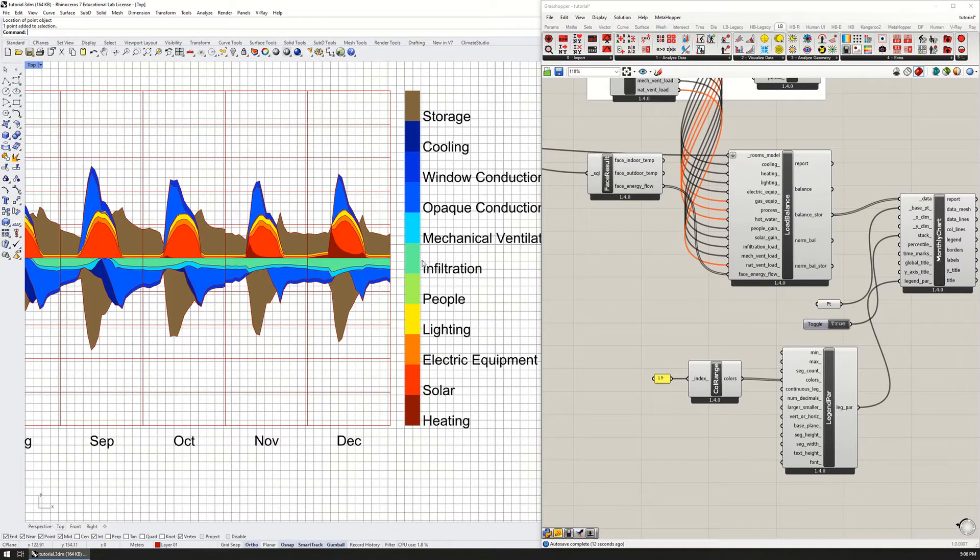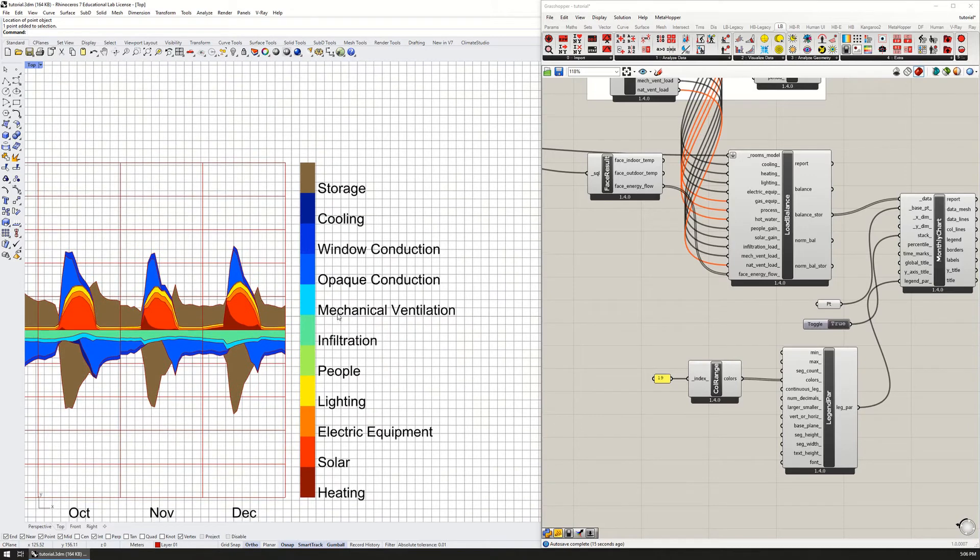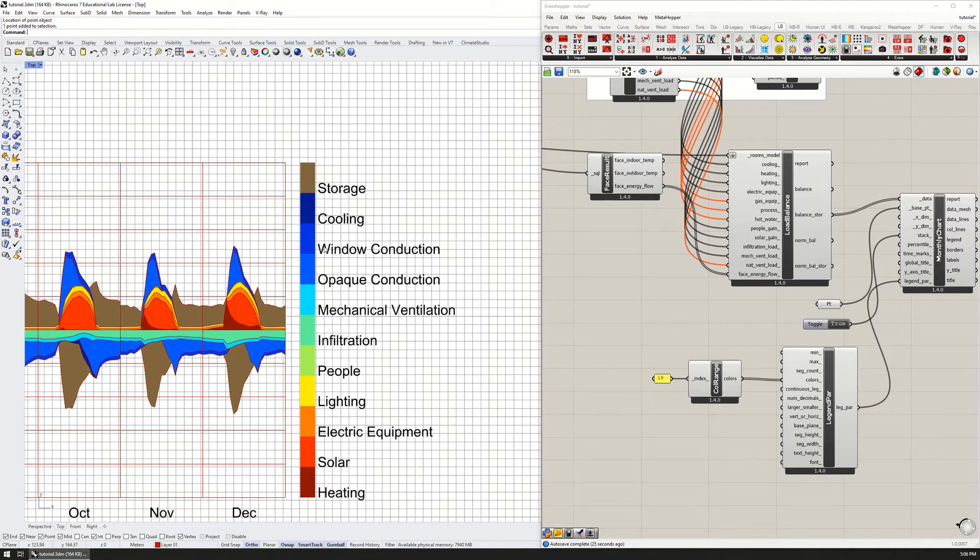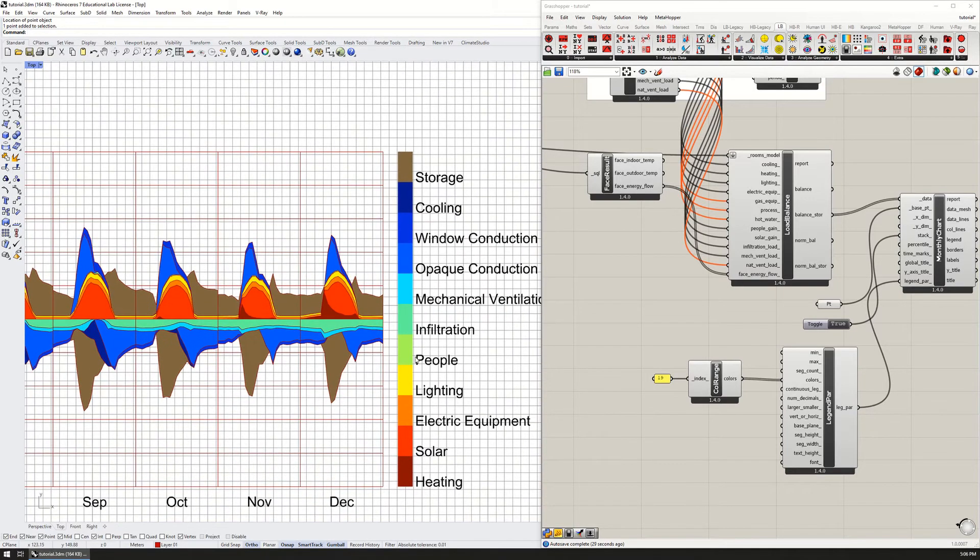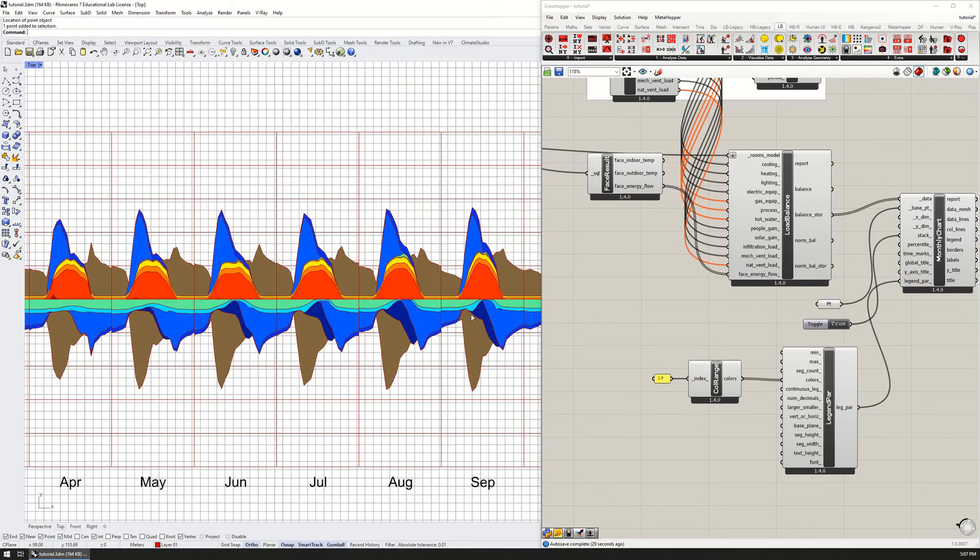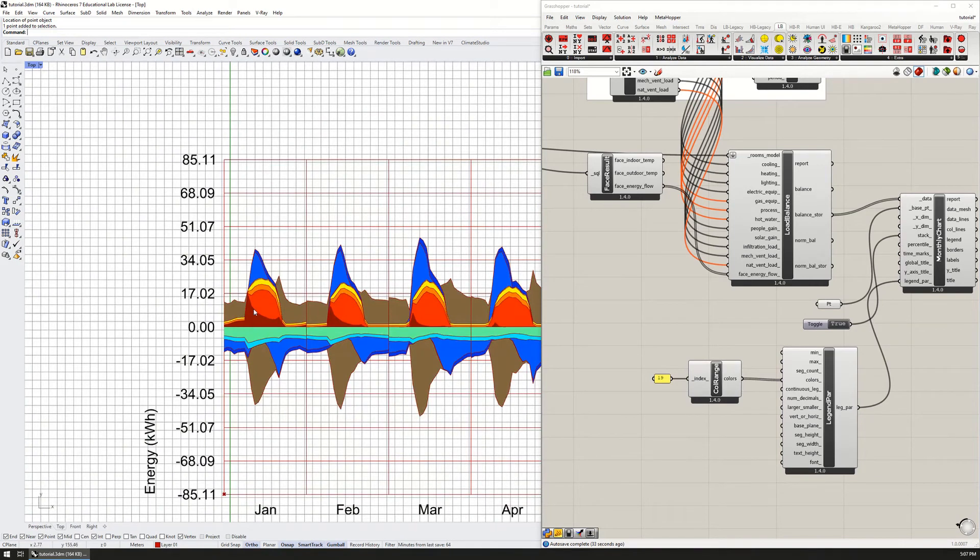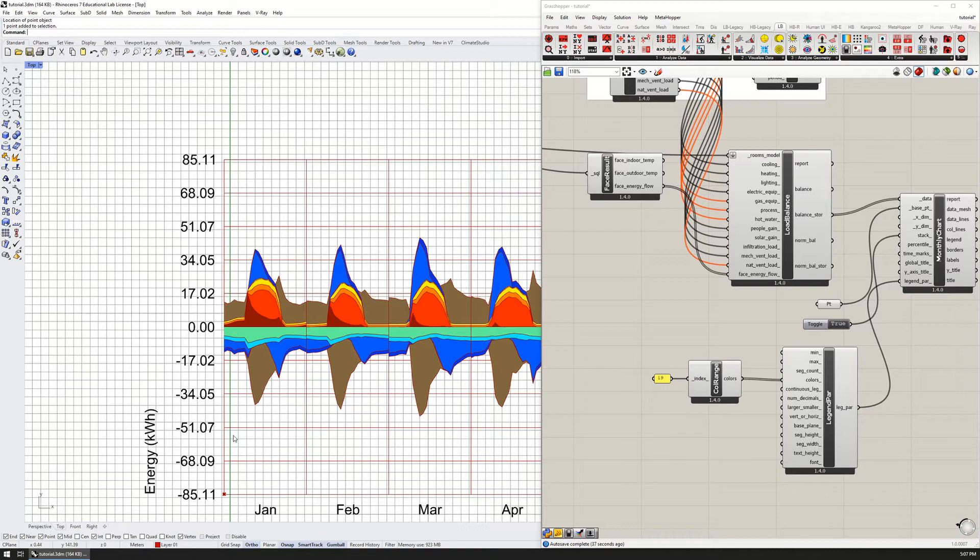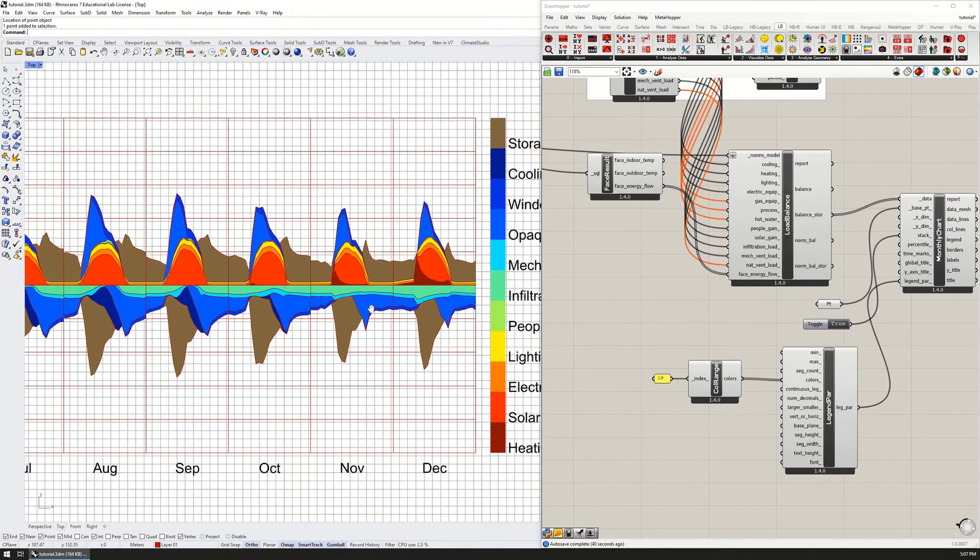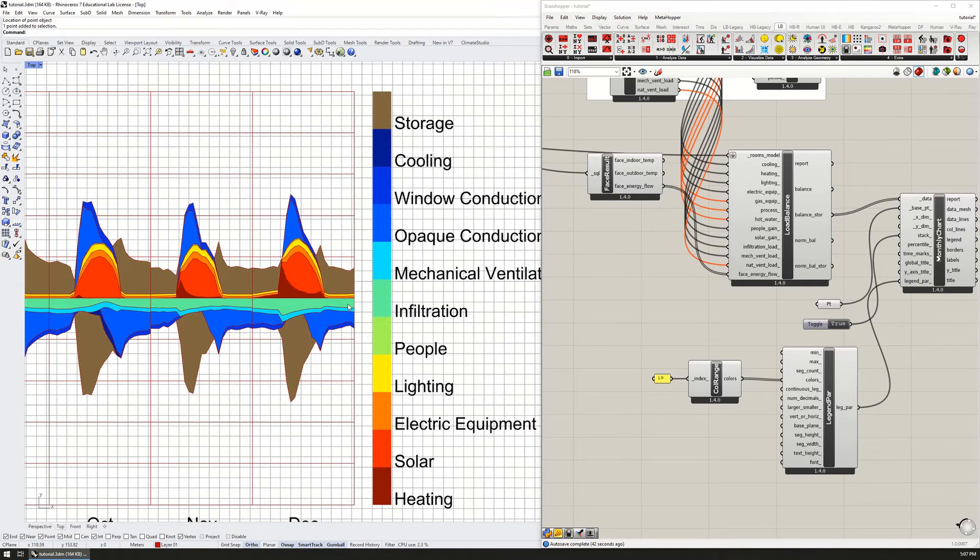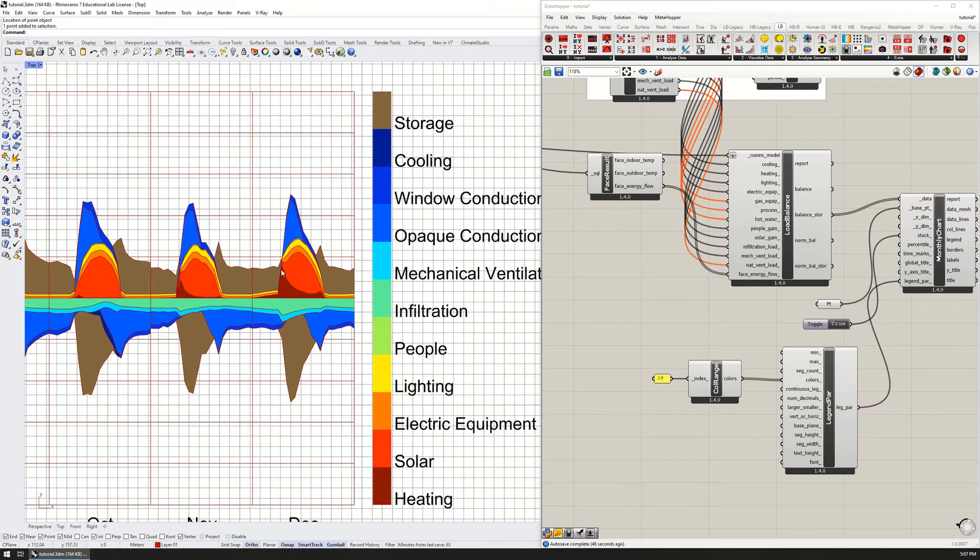You can see number 19 is the energy balance with storage - that's the sort of color palette they pre-baked for this, and I think it's pretty good. This helps me to see better the things that are gains, which are people, lights, equipment, solar and heating, versus losses, which are infiltration, ventilation, opaque conduction, window conduction, and cooling. Things above the zero line are gains to the room and things below the zero line are losses to the room.